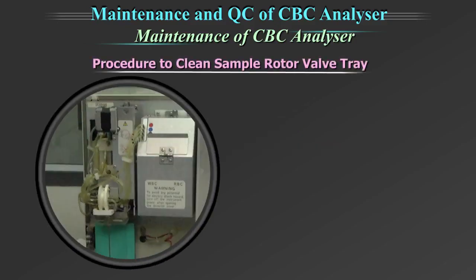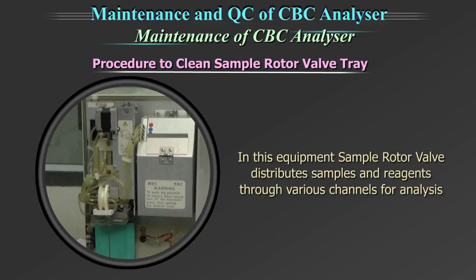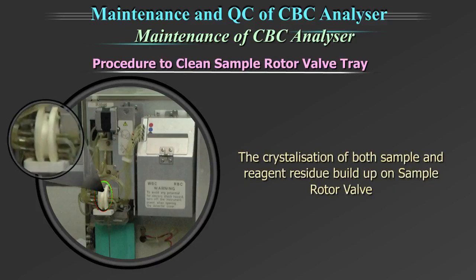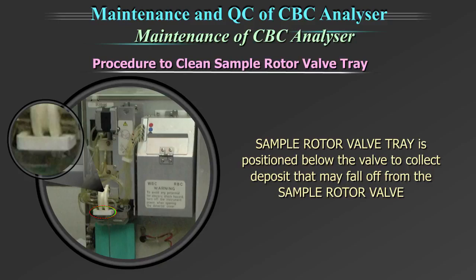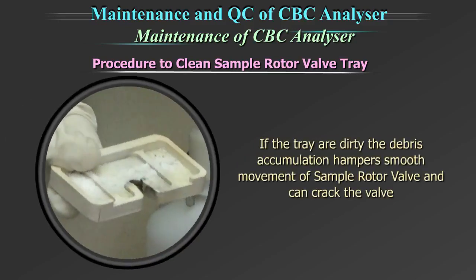Procedure to clean sample rotor valve tray. In this equipment, the sample rotor valve distributes samples and reagents through various channels for analysis. The crystallization of both sample and reagent residue builds up on sample rotor valve. The sample rotor valve tray is positioned just below the valve to collect the deposit that may fall off from the sample rotor valve. If the tray is dirty, the debris accumulation hampers smooth movement of the sample rotor valve and can crack the valve.